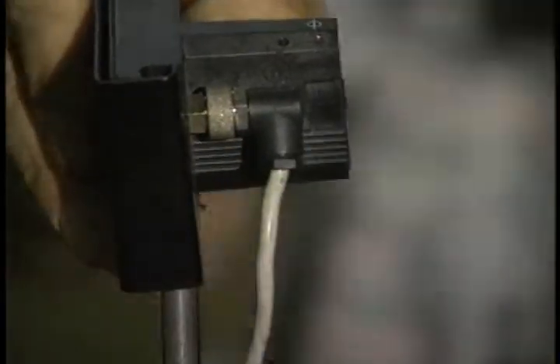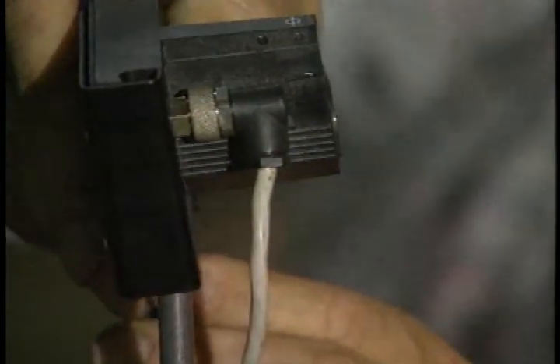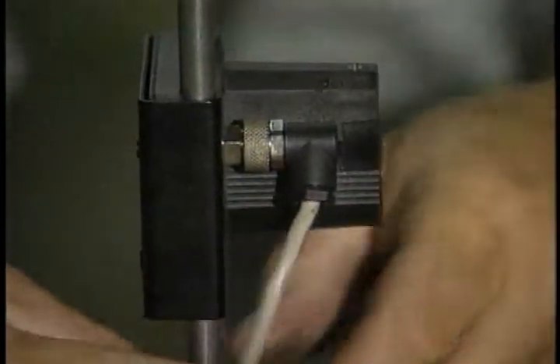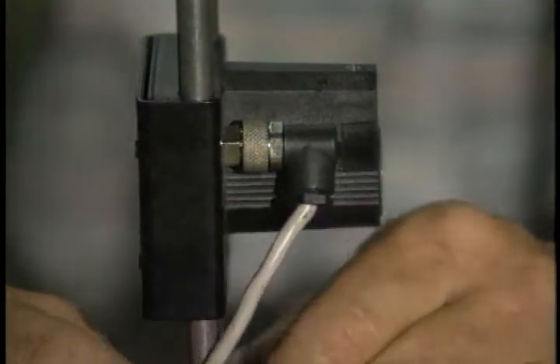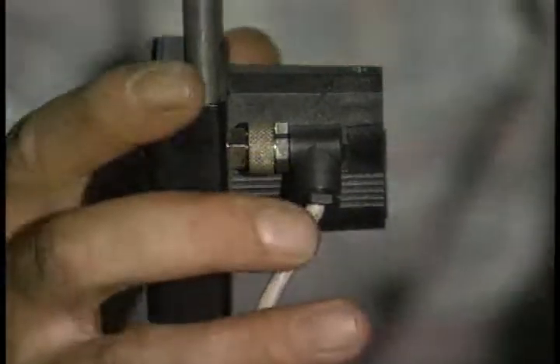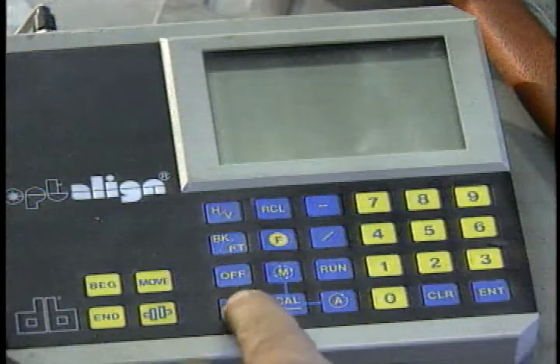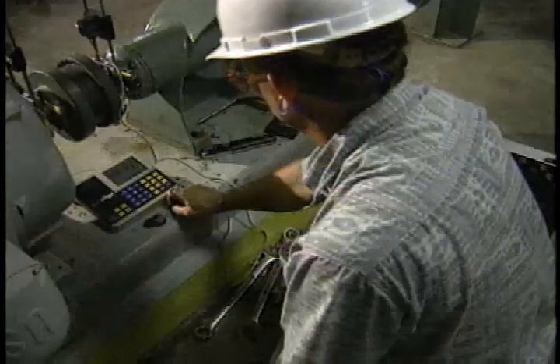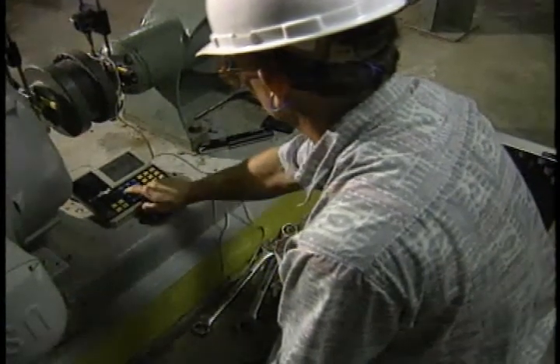Slide the heads as far down the post as possible while still providing space for the laser beam to clear the coupling. Connect the cable from the optic head to the computer, if one is provided, and secure the cable to the mounting bracket. The computer and the laser can now be switched on. If the computer does not come on, check the batteries and install new ones if necessary.